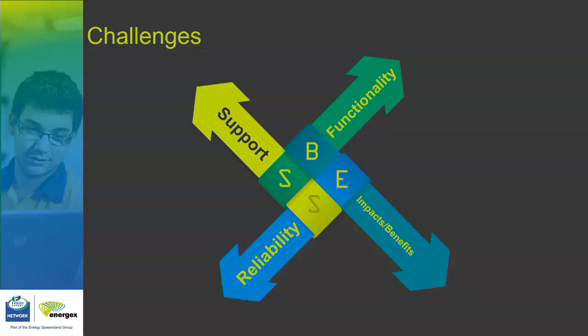A really interesting functionality we found that we dislike: a very early battery system would finish its discharge and then immediately charge at full power in the middle of the peak. Brilliant, I've just fixed the voltage and the loading for half my peak and I've just increased my peak. At that point in time, trying to get the manufacturer to change that setting was almost near on impossible. Now it's a bit different, but those are the sorts of things when it comes to functionality we've got to watch out for. What happens when there is an odd event?